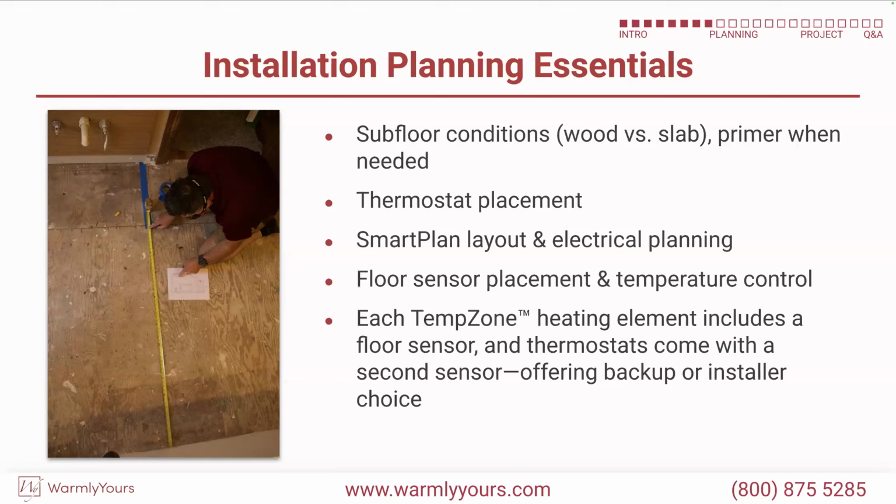Now we're going to be looking at a couple different plans, and please note coming up that we never heat 100% of the area. You're going to give us a drawing, and then we're going to give you a size of product that's already pre-sized. That's how we're able to ship the day you order. These are not custom sizes, but they're custom designs using various sizes and lengths to make it fit into your room. So keep in mind, give us the dimension of the room, not the area you're looking to heat. Give us the dimension of the room, and then you can mark if it's a separate area, but we're never going to heat all of it.